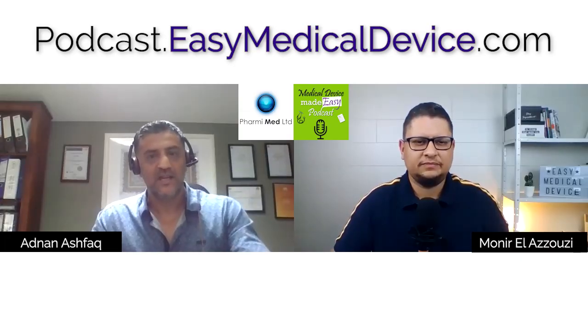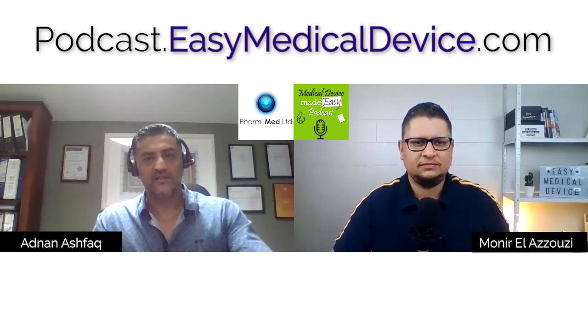And the determining factor is actually time. Some people don't know this. So, for example, you might have something like predictive cardiac arrest software. If the algorithm or software fails because of the calculation, and somebody goes into cardiac arrest, and the clinicians depend on the software to predict the cardiac arrest, and somebody dies because of a failure of not calculating the prediction correctly due to a failure of the algorithm, this is automatically Class C and Class 3, because we know that is death, but the time interval is immediate as well.